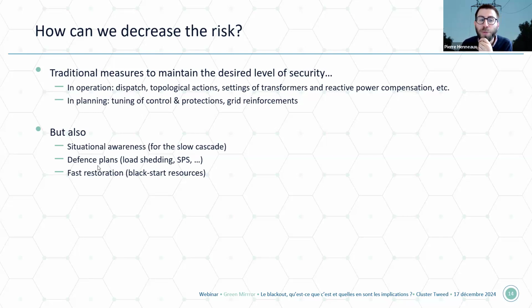So defense plans, basically to reduce the consequences. Once you start having a fast cascade, you can try to have good load shedding plans and special protection schemes to keep as much as possible the integrity of the transmission system, such that you will have load shedding, but you will be able to reconnect quickly if you stabilize the power system. And even if you have a blackout, if you have a good restoration plan, you will be able to resupply your customers quickly, which means that the blackout will not be so much a big deal.